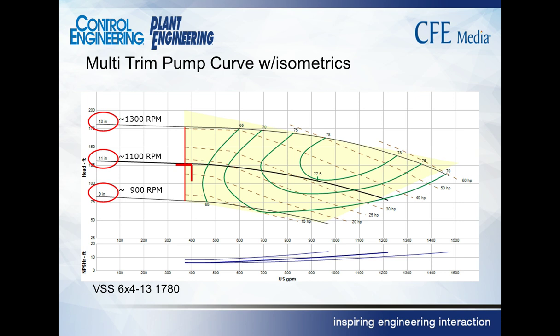Now, in most cases, it's not unusual for the efficiency to drop slightly when you reduce speed. In some cases, it increases. In a lot of cases, it stays just about the same. But that change in efficiency is going to be minor compared to the savings versus throttling because of the drop in head. Great, thanks. Another question, we'll try to get a few more in here.